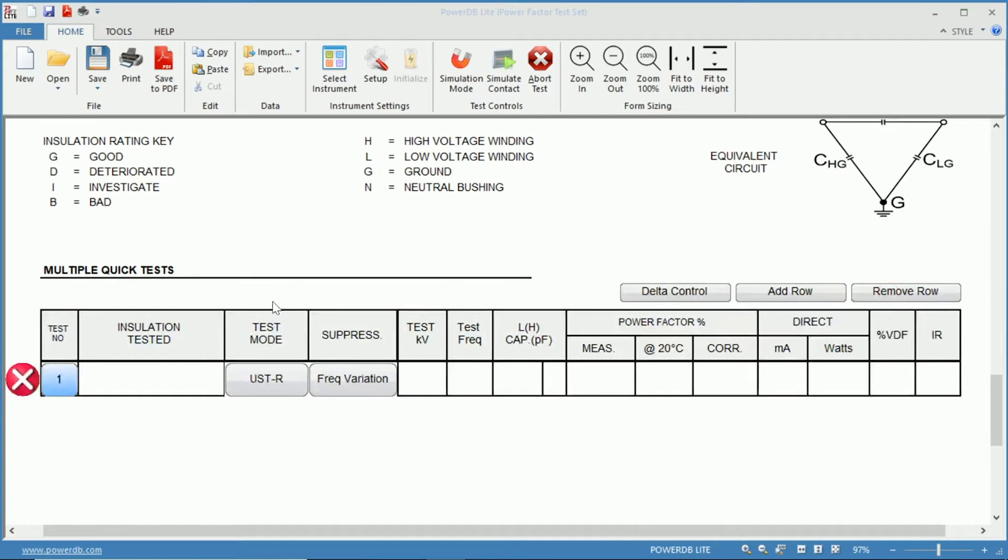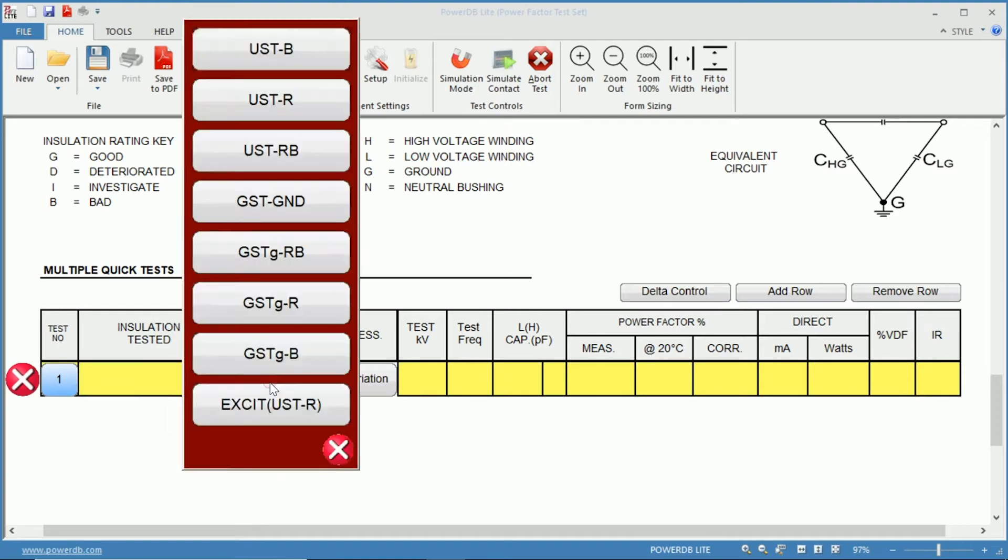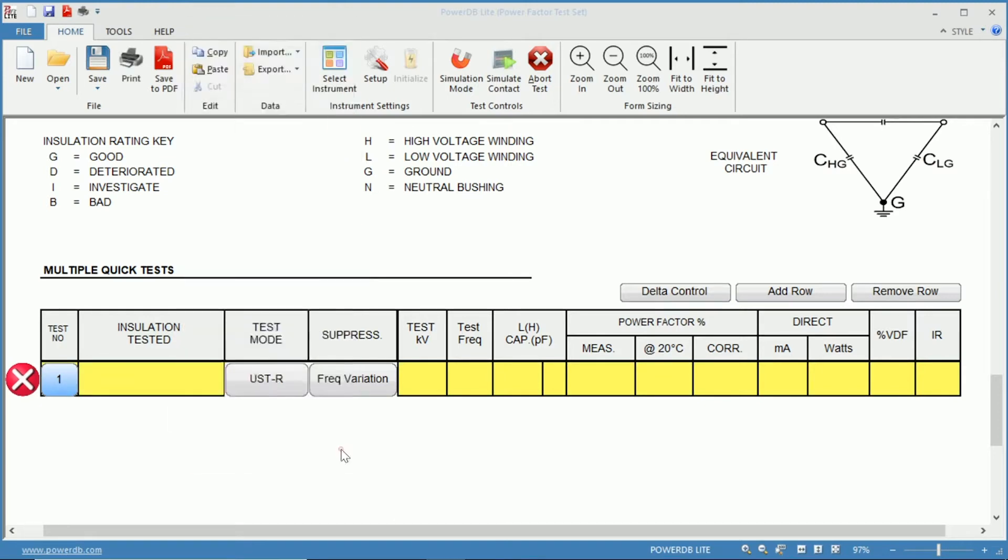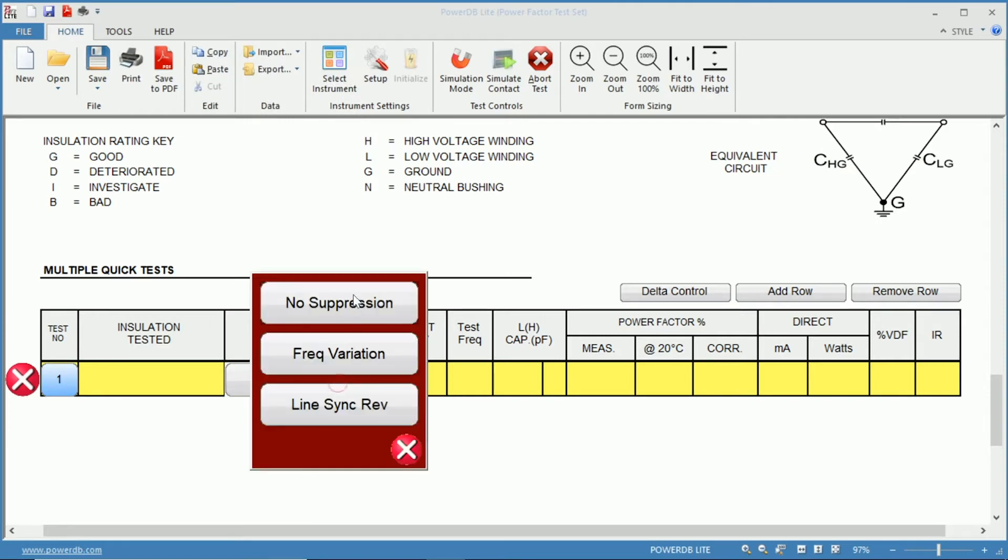You can designate what the insulation that you are testing is, the mode that you wish to test, so ungrounded test specimen or grounded test specimen. You can choose your mode of suppression, whether that be frequency variation, no suppression, so straight output, or line sync reversal.